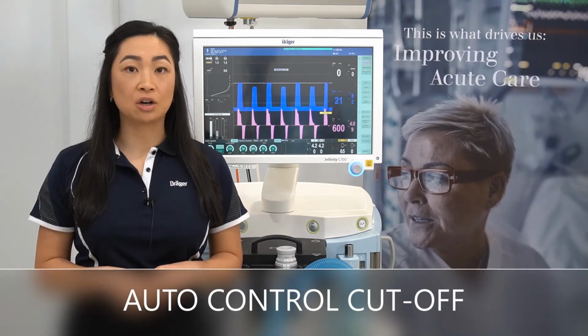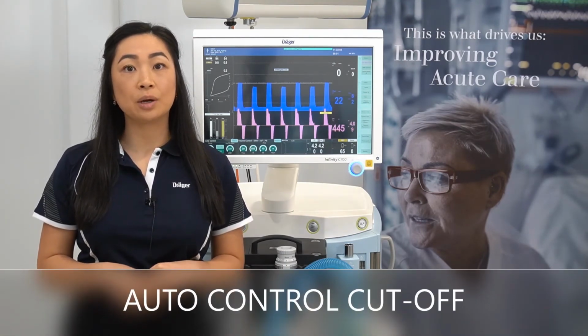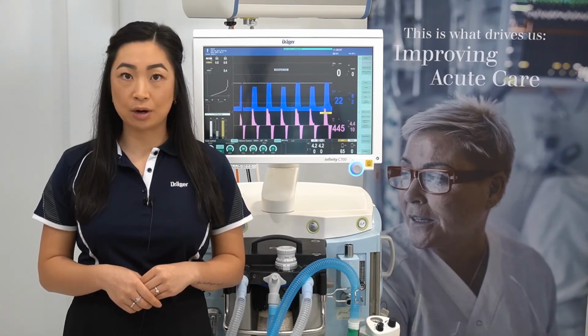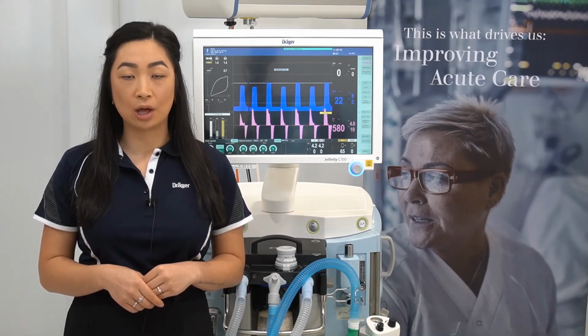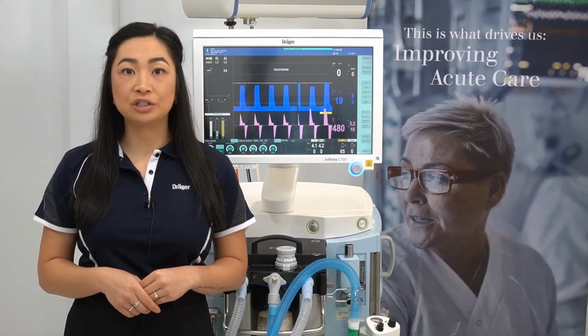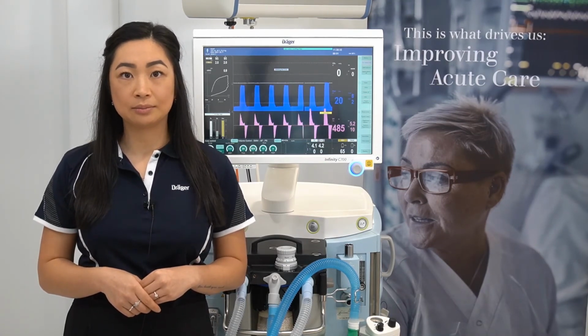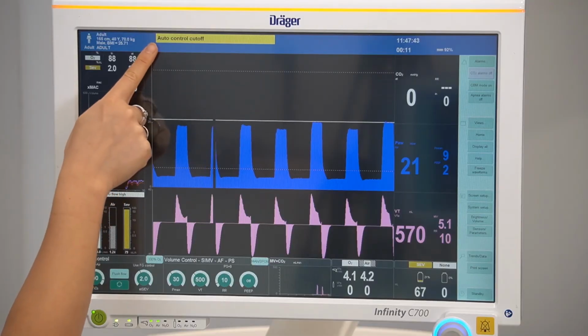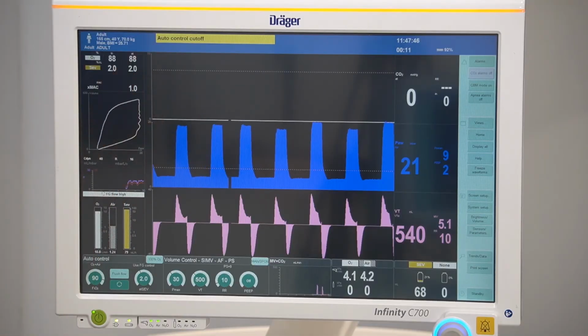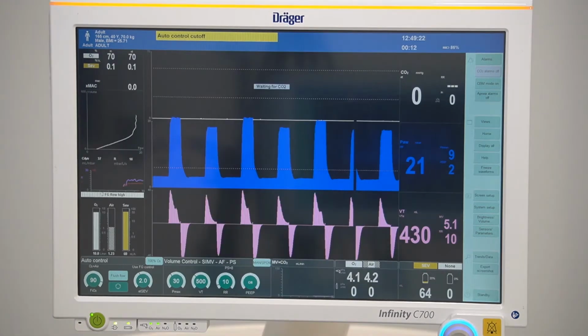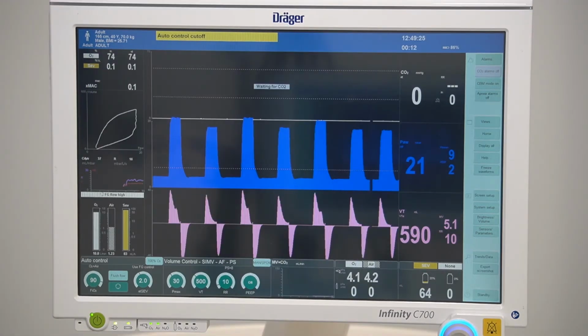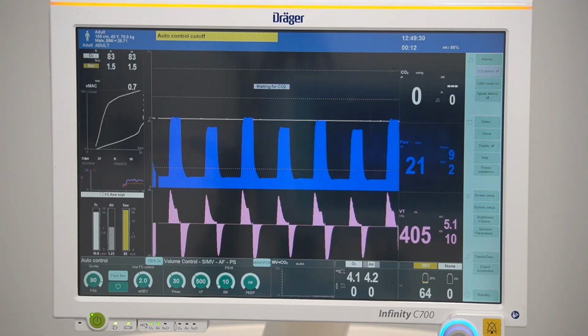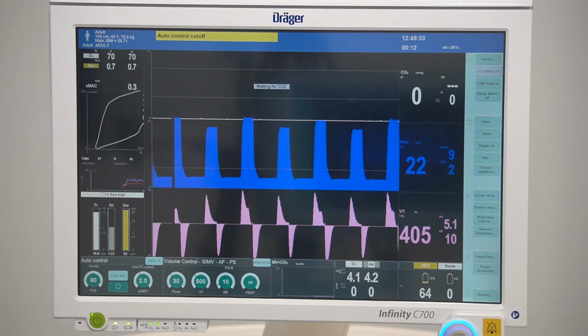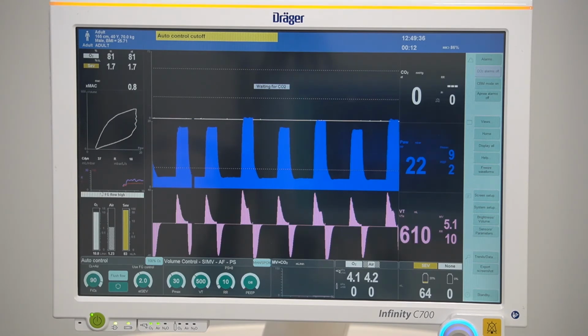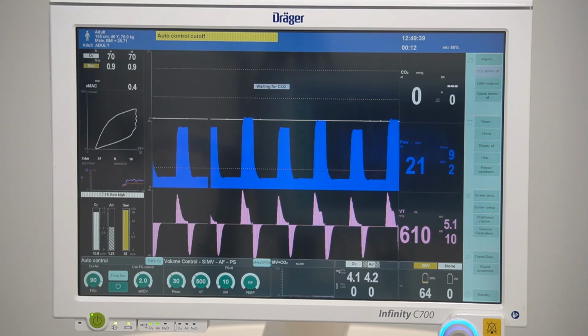Auto control cutoff on the Zeus occurs if you are in auto control mode and there is a discrepancy between the two sample gas analyzers. This is commonly due to a leak in the gas sampling line. You can see displayed in the header bar a message confirming auto control cutoff has occurred. The system will automatically switch to fresh gas delivery at 12 litres per minute so that the gas mixer ensures that the set target concentrations for oxygen and agent will be achieved. Ventilation and fresh gas mode are not affected.